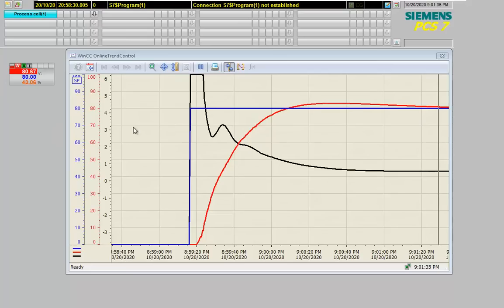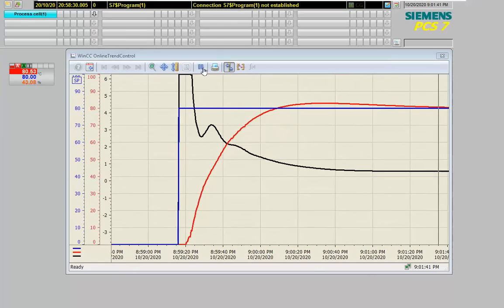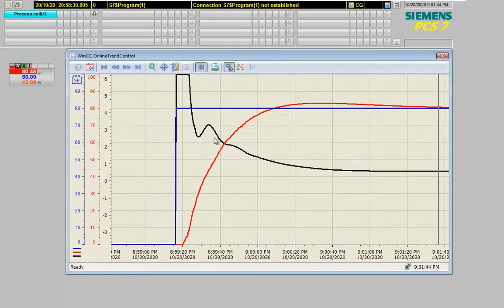the conservative PI parameter. And as you see, the aggressive PID is perfect. It's a perfect solution for quick startup. Your process should tolerate a slight overshoot. If you don't want this overshoot, you need to select the conservative solutions, and your response will be sluggish. It will be very slow, and you may not experience any overshoot.